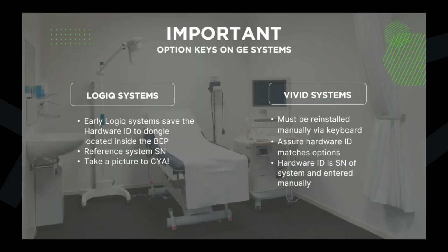And for the load software to those systems, it manually allows you to insert it. The load software to those particular Vivid systems asks you what the hardware ID is. Typically, it's the last 6 of the serial number of that particular system. You just enter it by hand. If you fat finger it and you go to enter the option string, in order to get back to that spot to reload the hardware ID, you're going to have to reload the system software again. So it's kind of a pain in the butt, but if you mess it up, that's why we always double check. That's why I'm having it up here on the screen. Double check that the hardware ID you're entering matches the 6-digit serial number on your system.